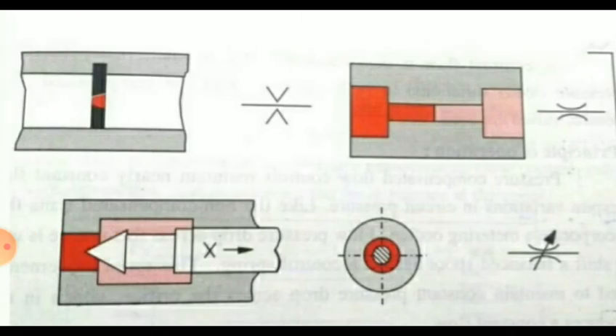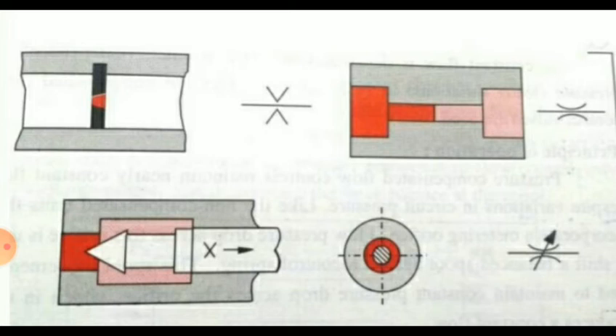Non-compensated flow control valves are simple valves that meter flow by restricting or throttling. Common non-compensated valves include orifices, throttle sleeves, adjustable needle valves, and gate valves. Due to their non-compensating nature, flow through these simple valves can vary at a fixed setting if either the pressure or temperature of the fluid changes. These flow control valves are used where accuracy is not important and heat generation through power loss can be tolerated.